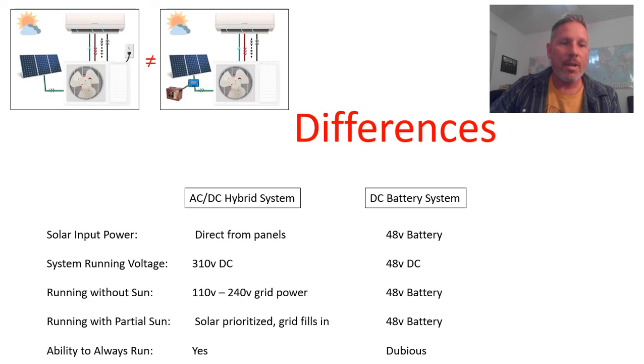Running when there's partial sun—that's where the beauty of this hybrid really shows its force. The solar is always prioritized. Let's say that the unit needs 850 watts in the summer to run and there's only 400 watts of solar. Well, the grid power will fill in for the extra 450 watts. But whatever amount of solar there is will always be prioritized, and the grid will only fill in.